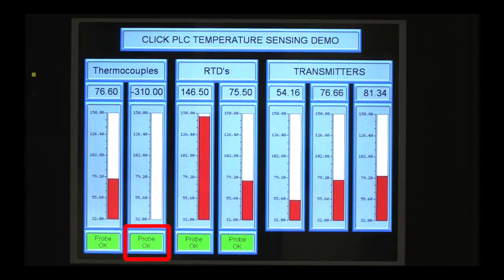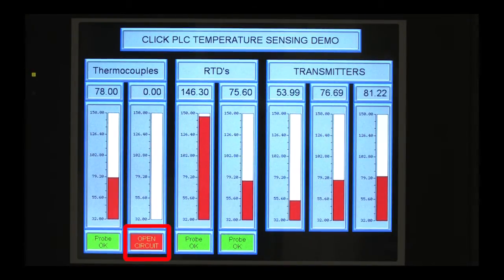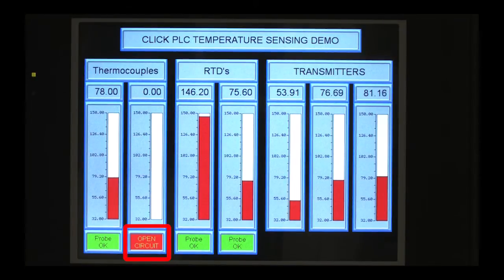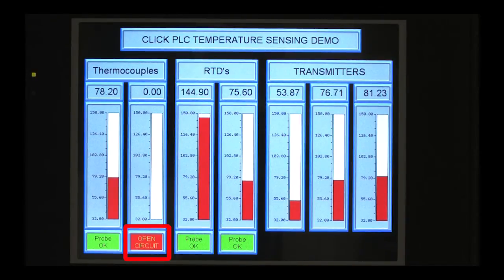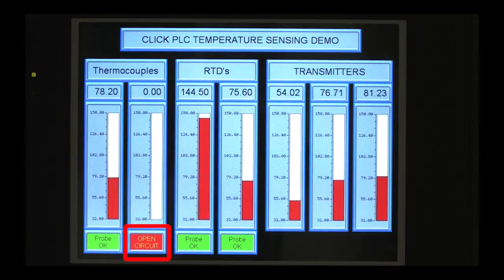If I disconnect one of the wires, the indicator that is monitoring that contact provided by the temperature module lights up, so I instantly know there is an issue with the wiring of the sensor. I love that feature. And again, we haven't written one line of ladder code to get these temperature values.